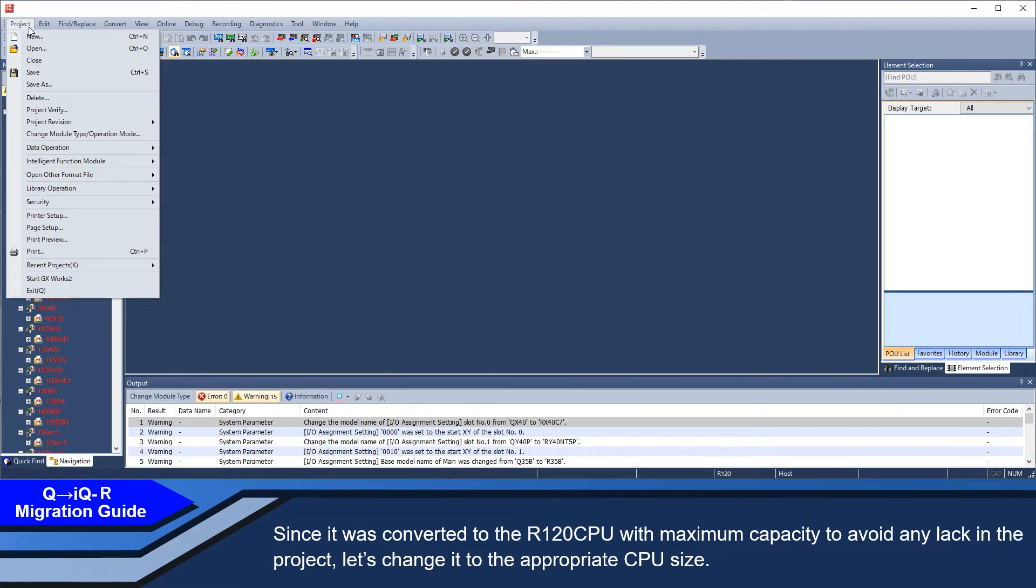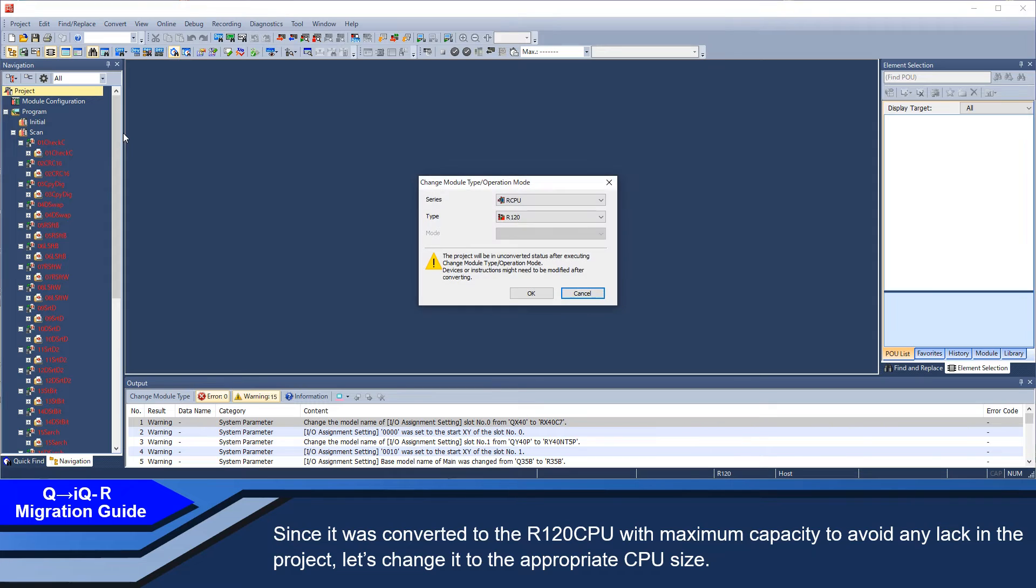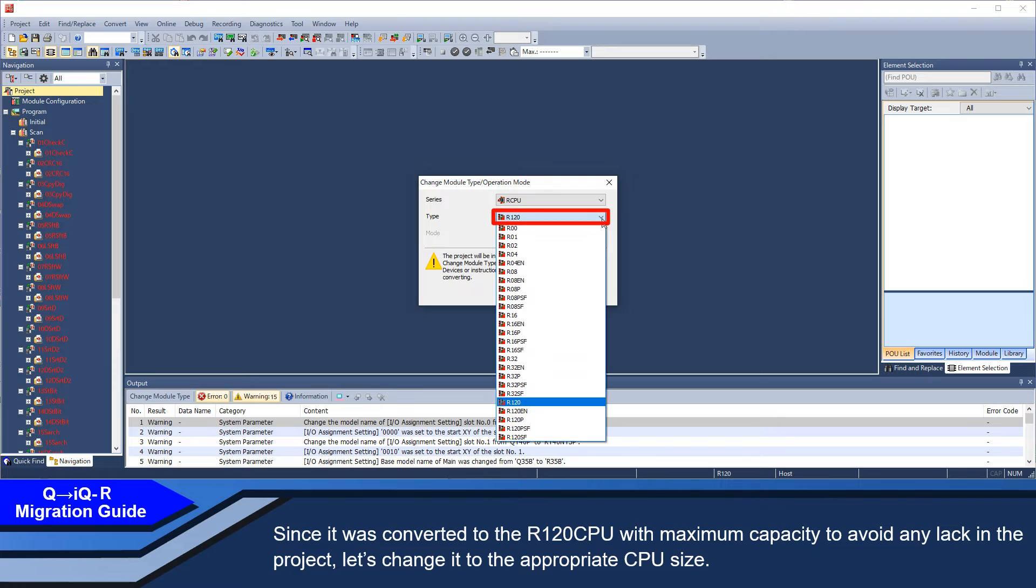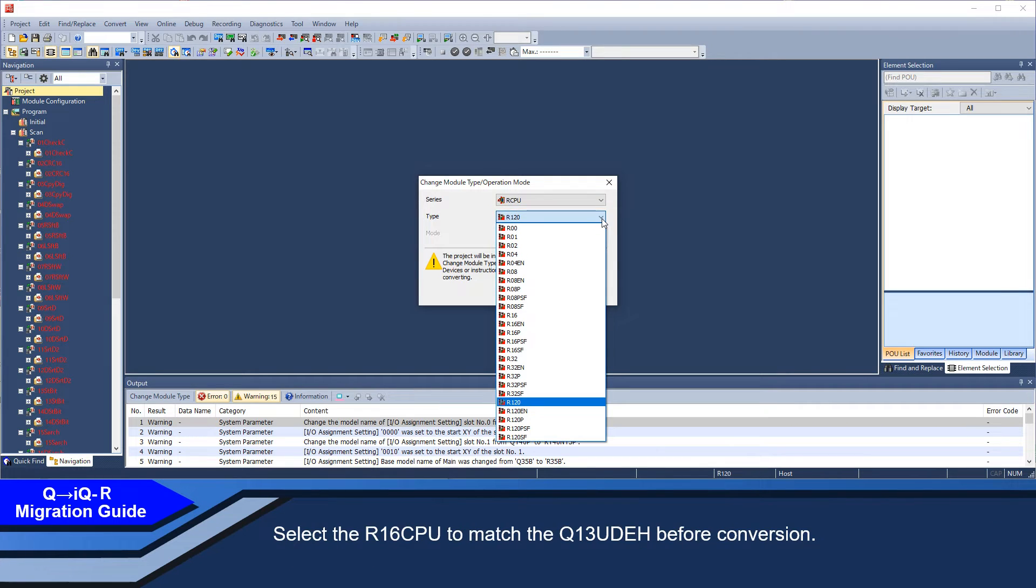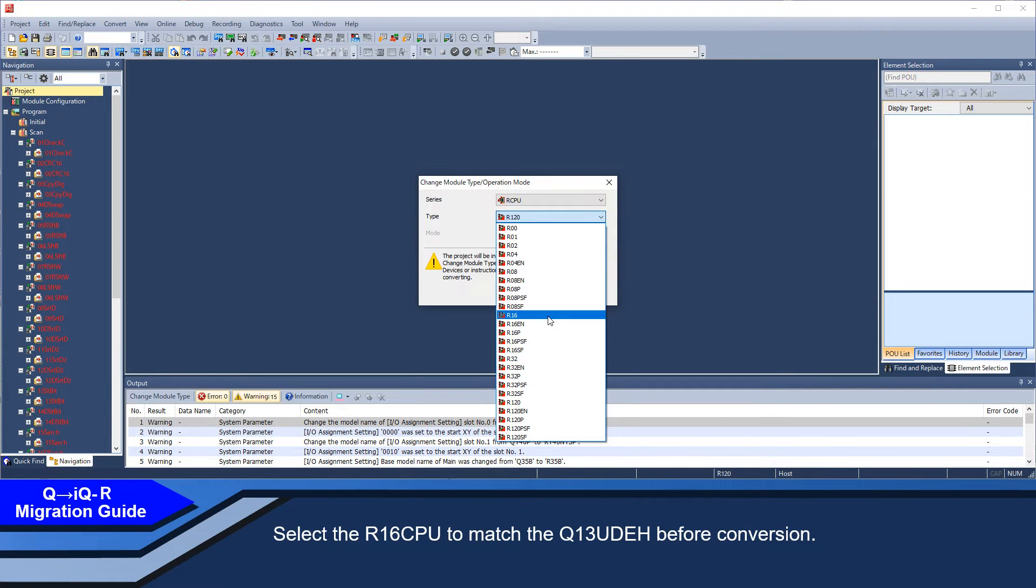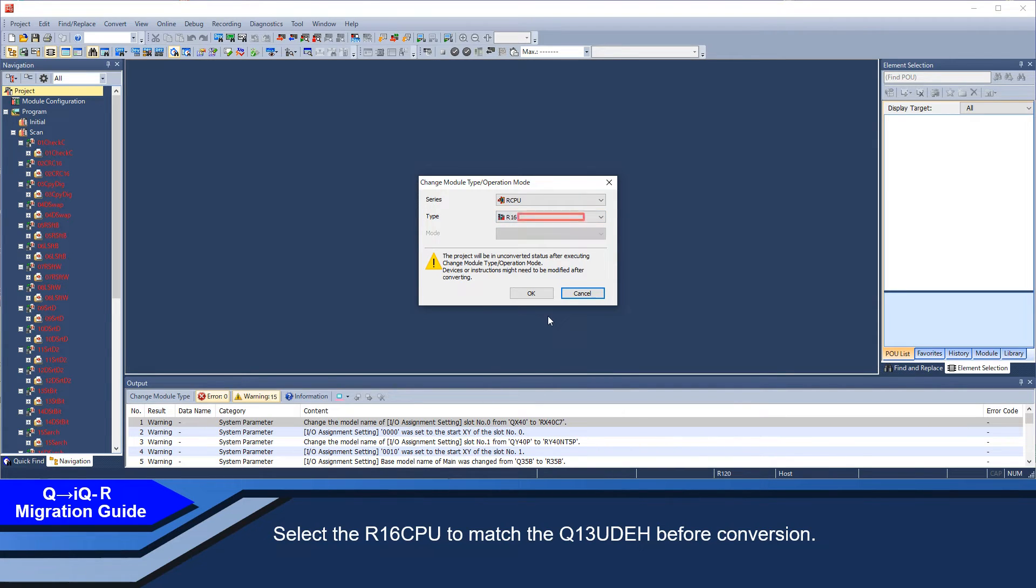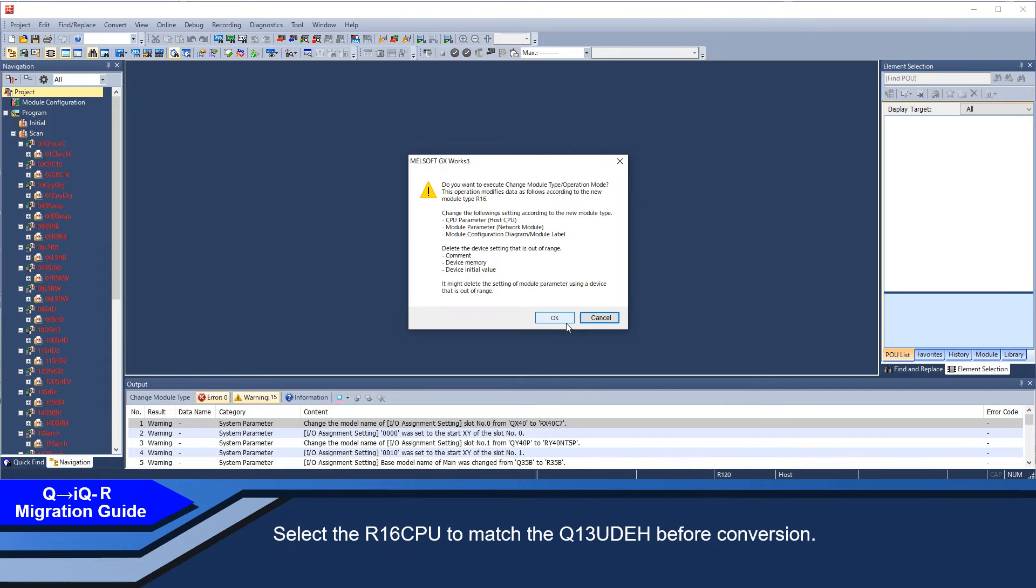Since it was converted to the R120 CPU with maximum capacity to avoid any lack in the project, let's change it to the appropriate CPU size. Select the R16 CPU to match the Q13UDEH before conversion.